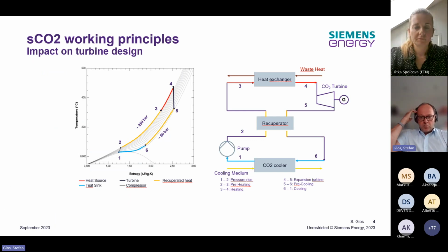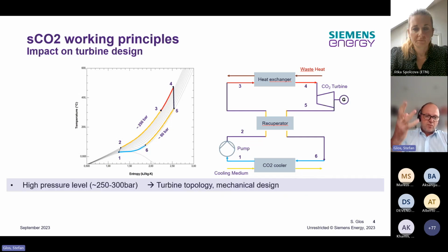Looking at the working principles of an sCO2 cycle, we see here a simple example of a recuperated cycle, in this case for a waste heat recovery application, and the process on the left-hand side in the TS diagram. From that, we can already derive some basic requirements and challenges. The first one is for sure the high pressure level in sCO2 cycles. At the inlet of the turbine, we are speaking about pressure levels of roughly 250 to 300 bar. Therefore, you need a mechanical design of the machine which is really suitable for that.